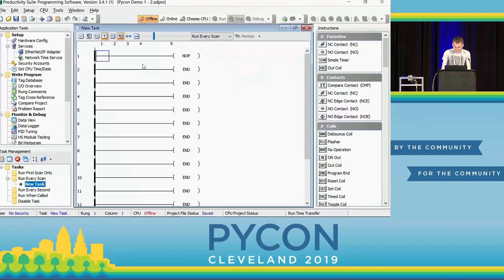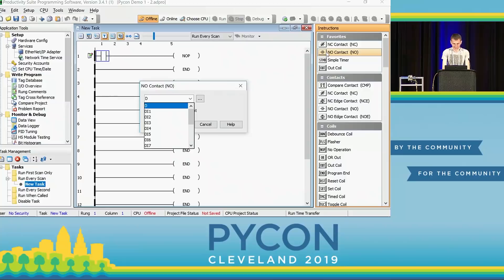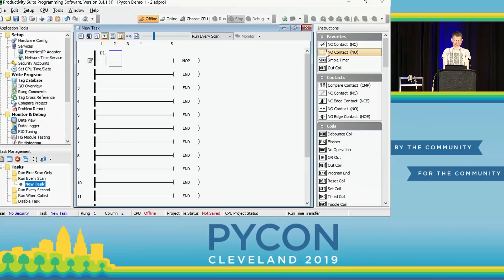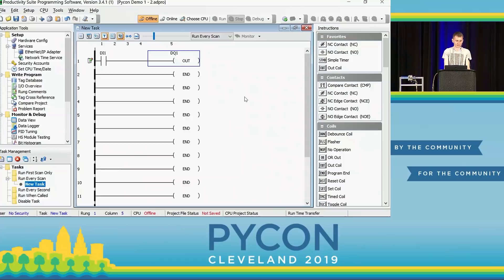This is the programming environment. On the very left is a big line — imagine electricity coming in, trying to travel down horizontal lines to the right. We get to place electrical circuit elements there. I'm going to put a normally open contact that looks at the variable DI1. It's basically like an if statement: if DI1 becomes true, current travels through; if it stays false, current can't get there. Whenever current gets there, we switch DQ1 to true. So we have the hello world of PLCs: if DI is true, make DQ true, otherwise both are false.